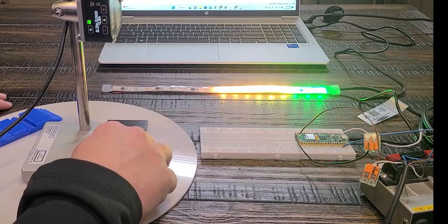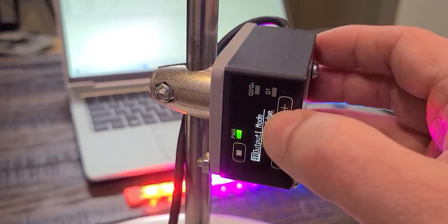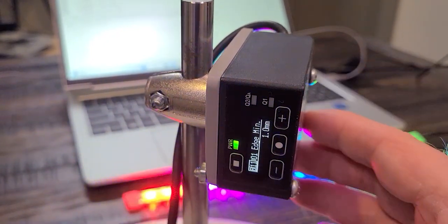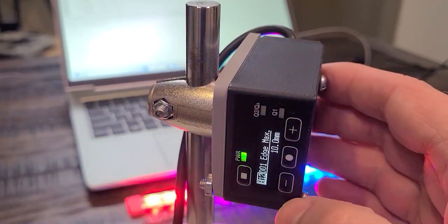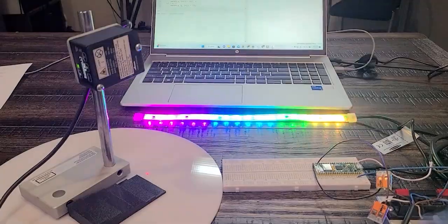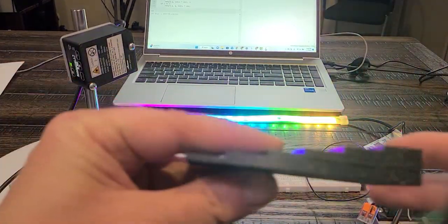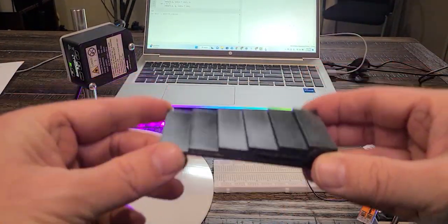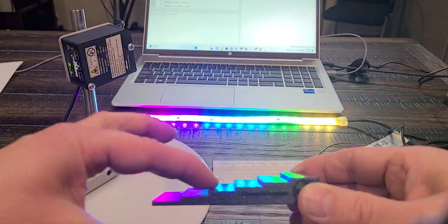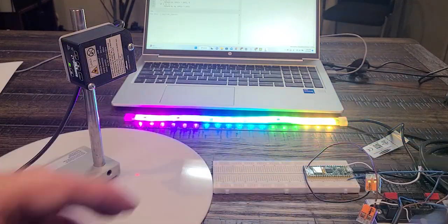Once you select the edge mode, you set the sensor a minimum edge height and a maximum edge height difference and the direction of the edge pulse. So if you have parts that are overlapped or stair-stepped, you can count them accurately. You could also have parts with varied size characteristics, or if there are gradual changes that you want to ignore, like a slope, and only detect an edge transition, this function could be useful.